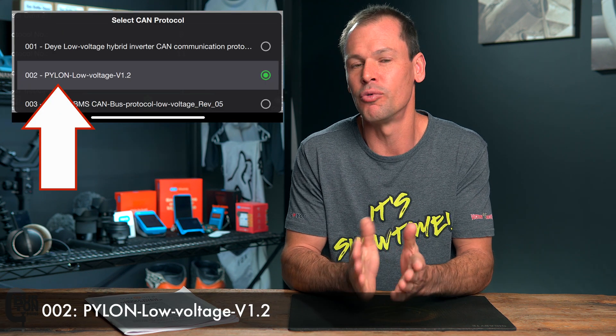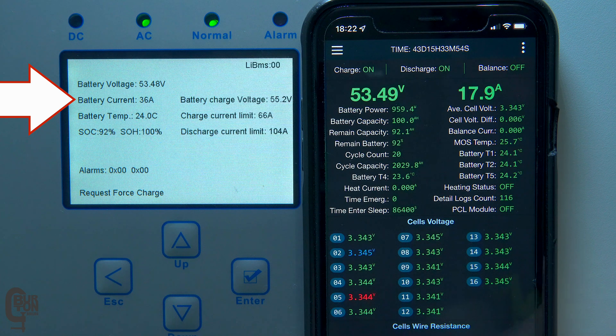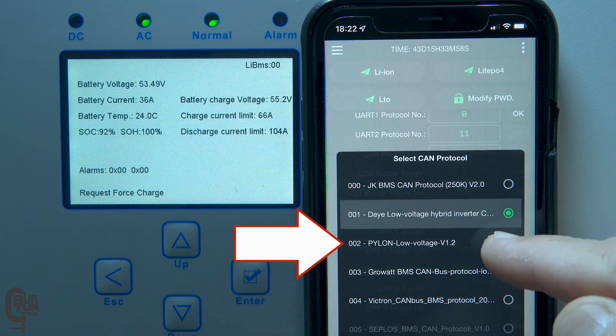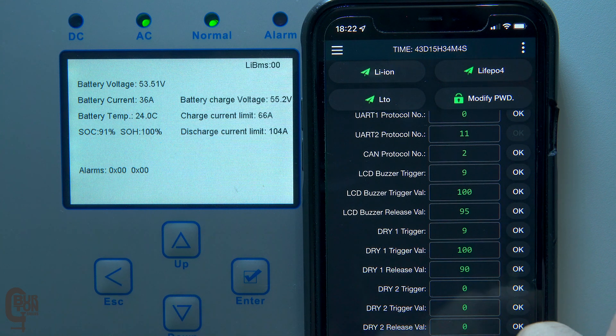Thanks very much to George GPR from Greece for being the first person to leave a comment in one of the previous videos, where he said all we need to do is set the CAN communication protocol in the BMS to 002 PYLON low voltage version 1.2 and the force charge request should disappear and everything should work perfectly. So let's go and set that and see what happens. Here the battery is at 92% state of charge and it's being charged at around two kilowatts or 36 amps total — 18 amps per battery — all from the grid. As soon as the Pylon CAN protocol is saved, the request force charge command disappears and the battery is allowed to discharge.